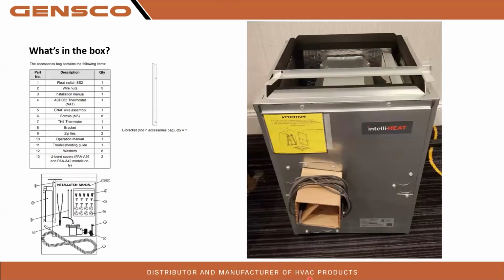So what's in the box? This is what you guys will get when you open up your coil, for those of you who haven't seen it yet. So you get your coil, obviously, and a goodie bag. On the coil, you also have the thermistors already pre-attached, so you don't need to take those off. They will need to be plugged into the control box, and we'll get through that a little bit more in a bit. But in your goodie bag, you're going to get this L bracket right here. What that's for is filling in gaps in front of or behind your coil, depending on the size of your equipment. So that little bracket is to help out with that, just for fitment issues.